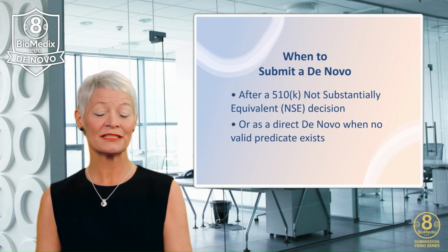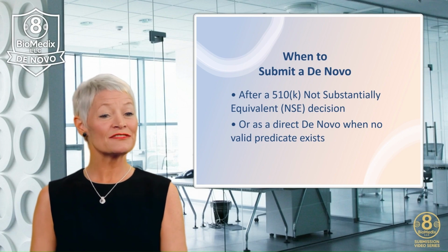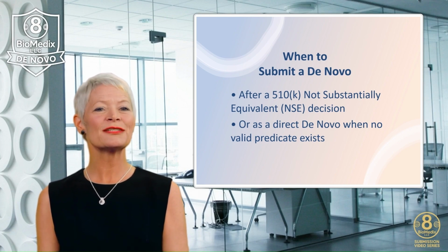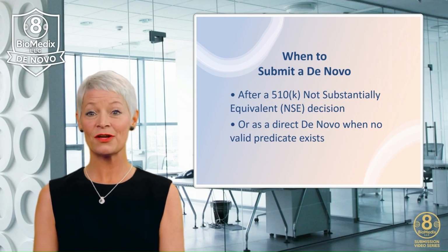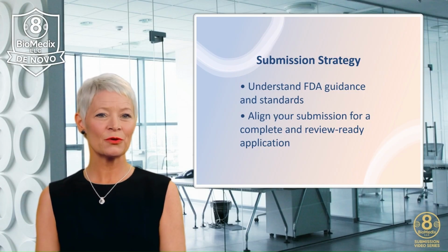You may pursue a de novo request after receiving a not substantially equivalent (NSE) decision from a 510(k) or as a direct de novo submission if you believe no valid predicate device exists.